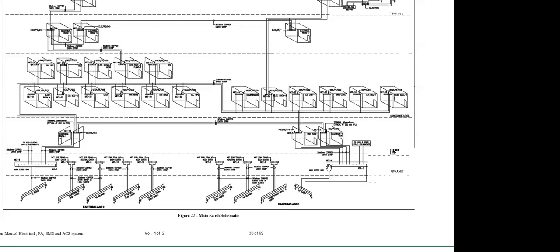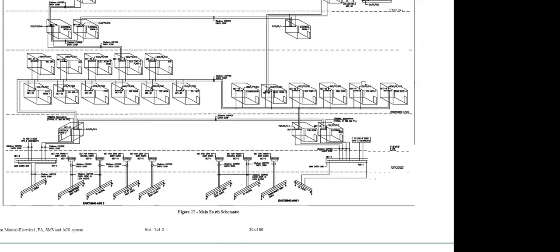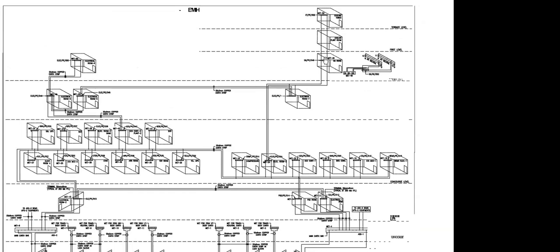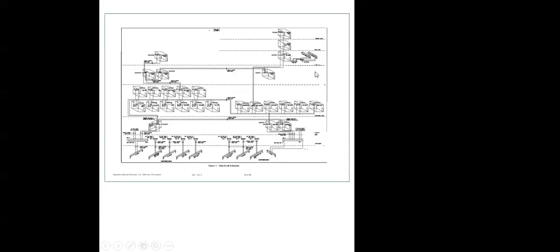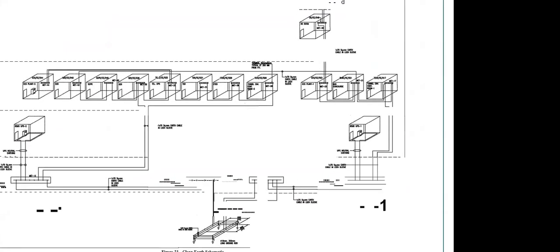And as you see here, from these main earth terminals, we have taken it through this bus and earthed all the equipments. No equipment here can be found without earthing. A similar circuit is there for clean earth also. In clean earth, the only important thing is we need to know the requirement of the other system users. For example, generally this clean earth requirement does not come from our side, I mean the HVAC side, but sometimes it happens that, for example, a precision unit is supplied by some other supplier, but as it is a part of HVAC, we may need to do the earthing for this. So in that case, we need to know what the requirement is, whether they need clean earth or main earth, and accordingly we need to do it.